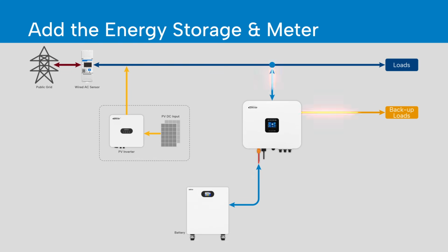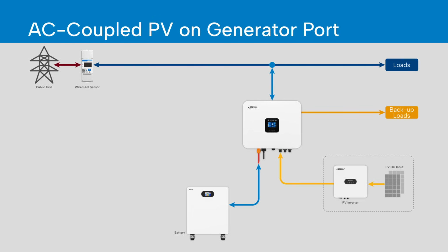Because the hybrid inverter is always active, it can continue supplying backup power when the grid is available. However, if the grid fails in this configuration, the normal load section will shut down. Connect the PV inverter to the generator port. This ensures the PV inverter continues operating during a grid outage. Solar power can still supply the load, and excess energy can flow through the hybrid inverter.